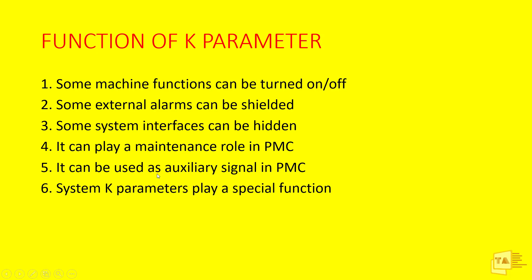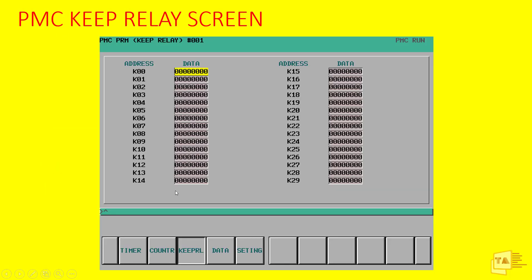There are normal K Parameters and special System K Parameters, both falling under the Keep Relay category — I'll show these later. For the PMC Keep Relay screen, if you open it you will find a screen with an address column and a data column. For example, K0 represents an octal number system where K0.0 through K0.7 are 8 bits, then K1.0 through K1.7, and so on. From this screen we can bypass signals. In newer FANUC models and DCS PMC, the Keep Relay screen looks the same.